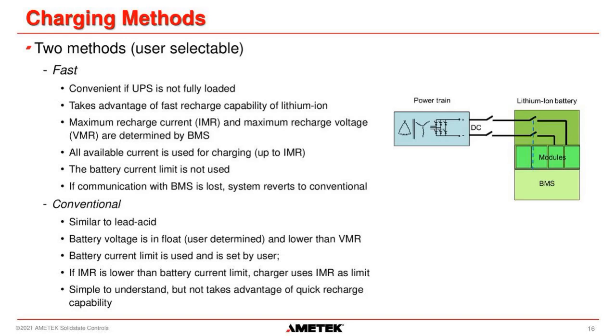In the conventional mode, the battery current limit is used and can be set by the user. Once again, unless the IMR required by the battery is lower than the battery current limit that the user sets, we don't want to exceed the IMR because it will trip the breaker on the battery itself. This conventional mode is easier to understand for legacy systems, or for the way the market is right now, but it does not take advantage of the faster recharge times of a lithium-ion battery.